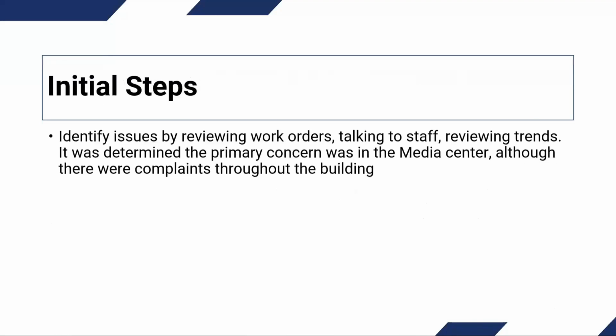Again, our initial steps are always going to be similar. We needed to identify what the actual problems were by looking at the work orders, talking to the staff, reviewing the trends. And in this particular case, the primary concern was the media center of the library. Although we did have sporadic complaints throughout the buildings, the main issue was the library in this particular case. Again, on all of our initial steps, you'll see that we're not relying on what somebody's telling us the issue is. We're trying to determine by a systematic means what the actual problem is on the project.